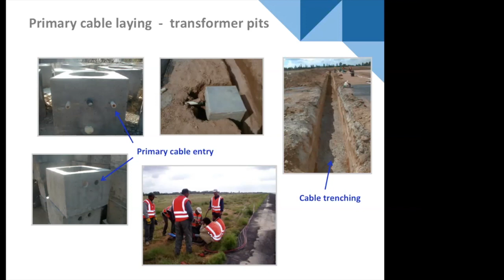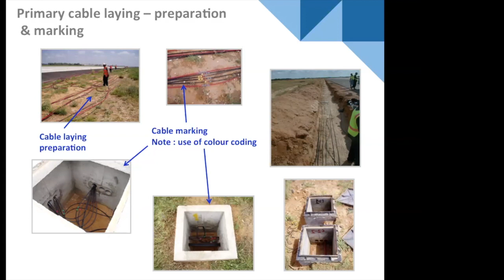But one of the key issues that we have to consider is that these transformer pits, if you've got what is called a pit and duct system, there's some ducts and that's a pit, then this becomes part of the airfield drainage system by default. Now, ideally, we want those to be nice and clean and dry. The reality in most of the world, that's not the case. So that's a knock-on effect to maintenance, which we have, and the insulation resistance failures, which we can discuss a little later.